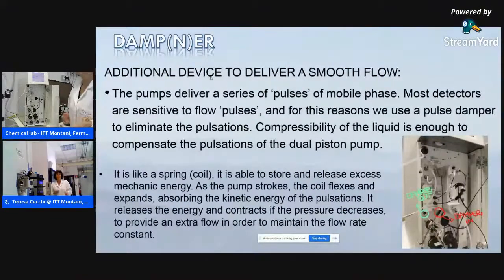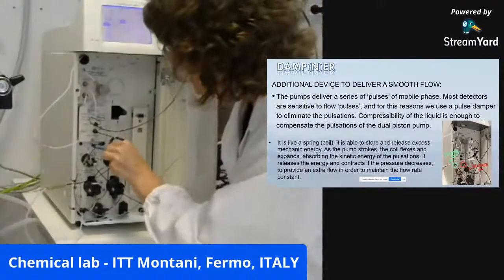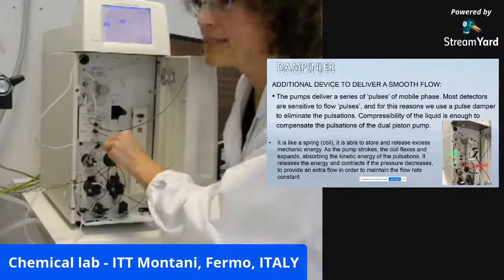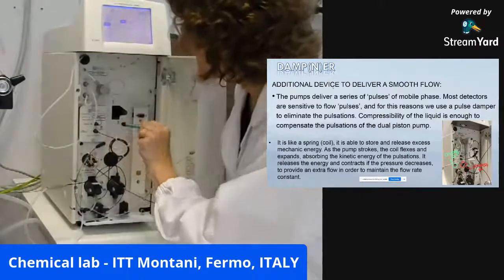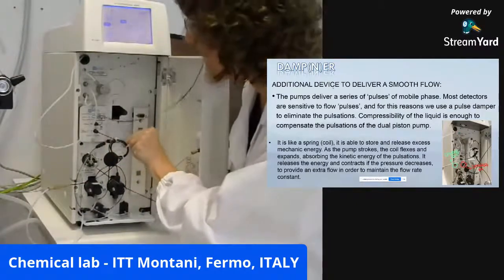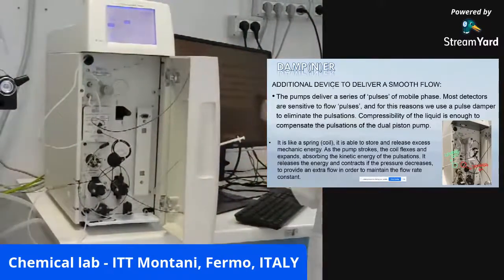Well, I told you that we have two pistons to provide us with an almost constant flow, but the flow is actually not completely constant. The pump delivers a series of strokes, of pulsation. For this reason, after the pressure sensor, the eluent will get inside here, the dampener. You cannot see the dampener because it is behind this front panel. But the damper is like a coil, a spring.